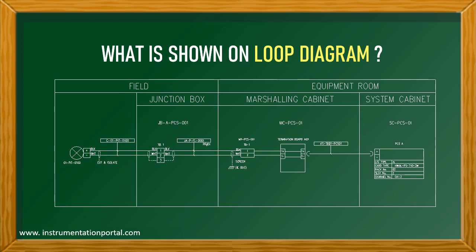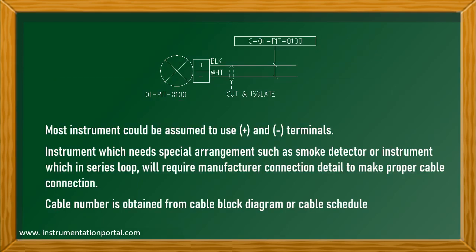Next, we will discuss how these information are obtained. In the instrument section, most instrument terminal numbers are assumed to use plus and minus terminals. However, instruments which need special arrangement, such as smoke detectors, or instruments which are in series loop, will require manufacturer connection detail to make the cable properly connected. The cable number is obtained from cable block diagram drawing.